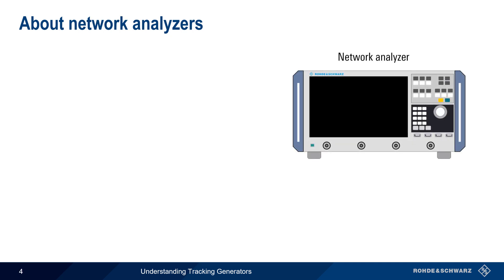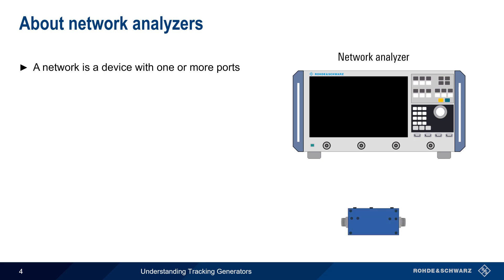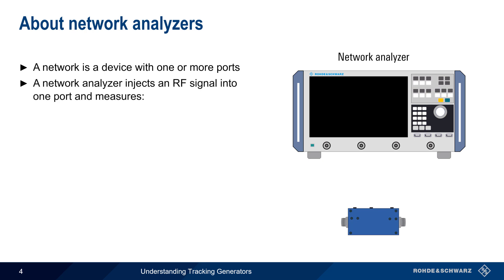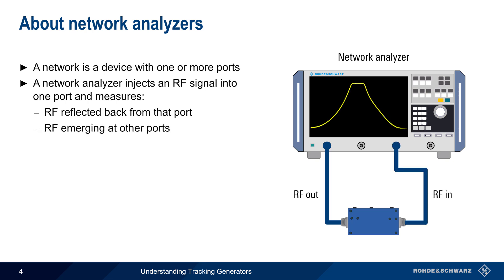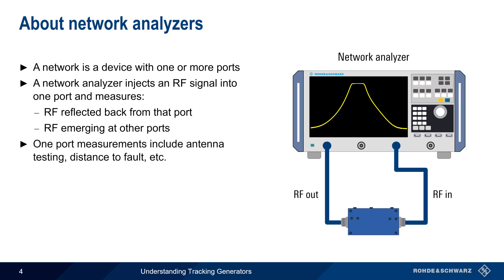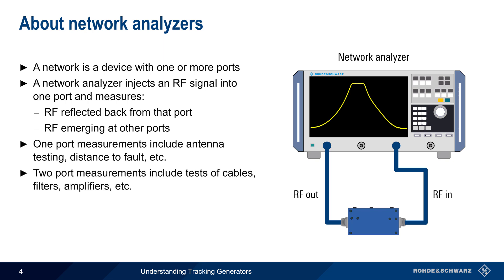Another common radiofrequency measurement instrument is a network analyzer. A network is a device with one or more ports that can absorb, pass, or reflect radiofrequency energy. A filter is a good example of a two-port network. Network analyzers usually have multiple inputs, and they perform measurements by injecting a signal into one port, then measuring the signal reflected back from that port and/or the signal emerging from the other ports. Common one-port applications include antenna testing or distance-to-fault measurements. Common two-port applications include characterizing cables, filters, amplifiers, etc.